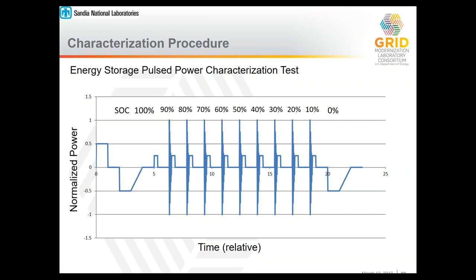Now, we run tests at each state of charge from 90% to 10%, and then have a conditioning step on each side. So these are 9 tests run from here to here. What essentially they amount to is a discharge by 10% state of charge at a low rate, a rest period to let the batteries cool back to a nominal temperature, and then a series of charge and discharge pulses. I'll go over exactly what that looks like on the next slide. But essentially what this does is it takes a snapshot of the device's maximum performance at that state of charge.